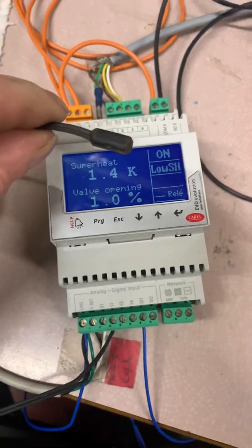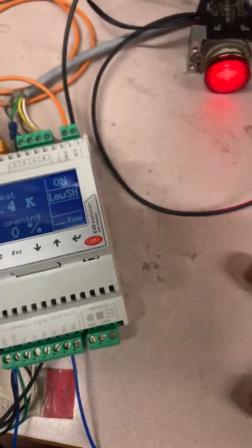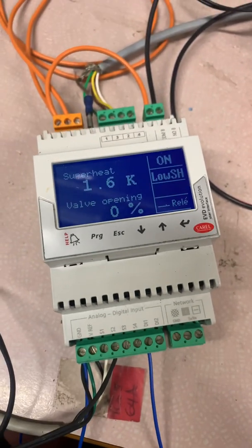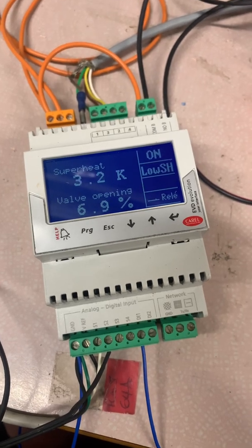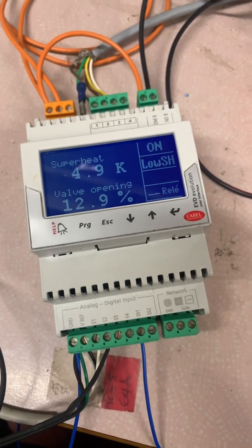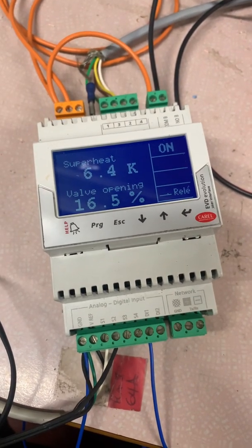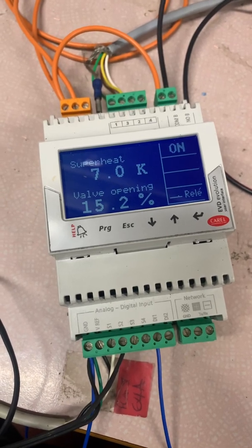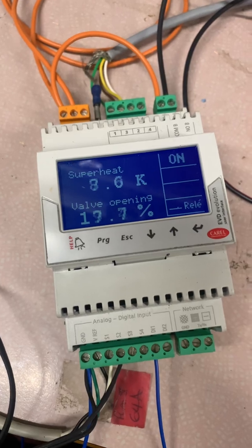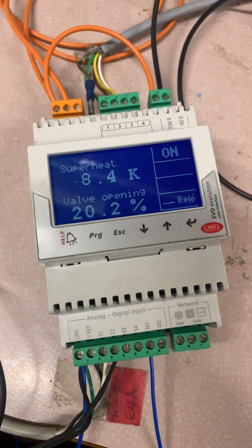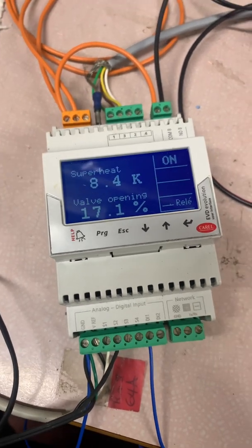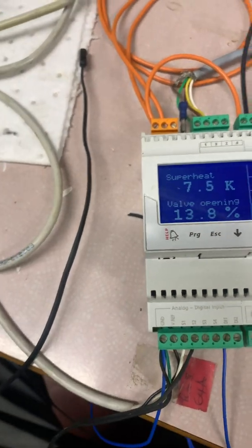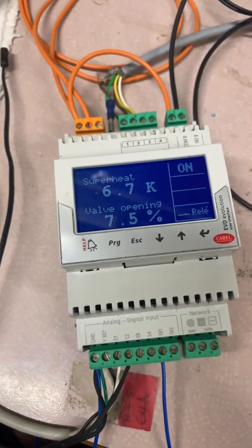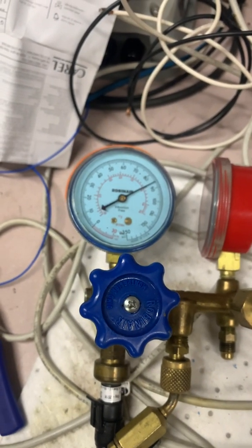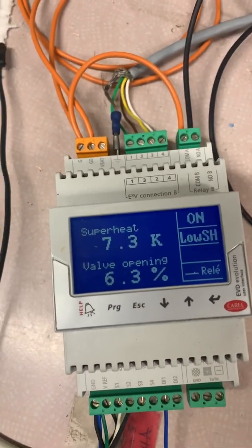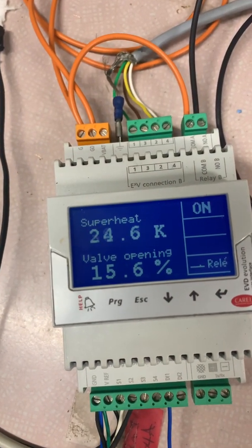And then I could maybe, if I get my probe, put it in my mouth, get it hot. I'm heating it right up now, at the same pressure. Yeah, so that same pressure but having more heat on my probe is causing it to respond. What if I dropped the pressure and kept the same heat? Let's see if I can get that, if I let the pressure out now. Right, and then that should start seeing that my superheat's going massive and I open my valve up.